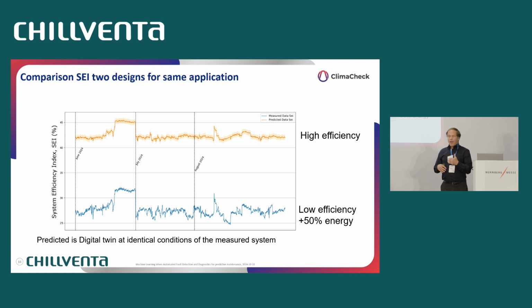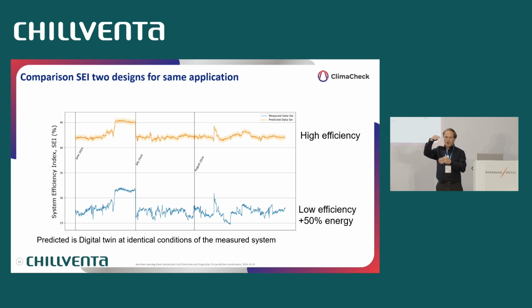This is showing where we train on the SEI. SEI is System Efficiency Index. So instead of talking about COP, which is changing with each operating condition, we like to talk about System Efficiency Index, which compares the COP with a Carnot cycle at the ambient conditions you're working with. So if you have a chiller, you look at the average cooling water, average chilled water. If you have an indefinite heat exchanger, indefinite flow, that would be the temperature level this system is working with. Then you can split your efficiencies on condenser, compressor, evaporator, and cycle.